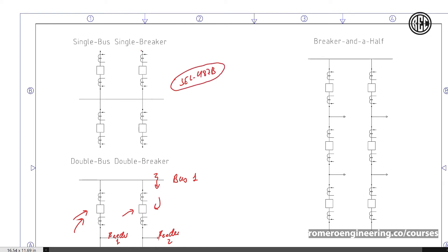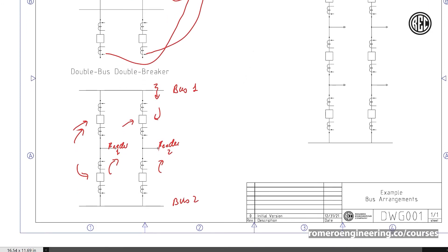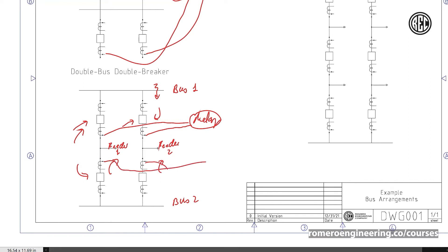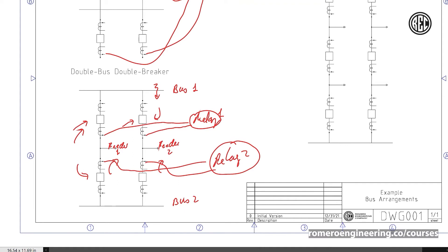For bus protection, we would typically use something like an SEL487B — a commonly used bus differential protection relay. In the straight bus configuration, because there's only one bus, we need only one protective relay (or a primary and backup). For the double bus, double breaker configuration, we now need two bus differential protective relays: relay one connected to the CTs for bus one, and relay two for bus two. So not only do you have more breakers, you also need more protection — one relay for each bus in the substation, making the design more complex and expensive.